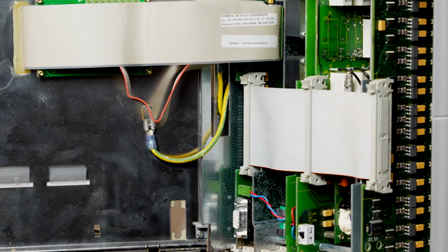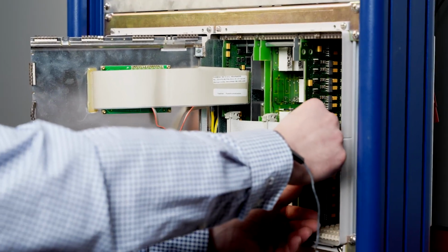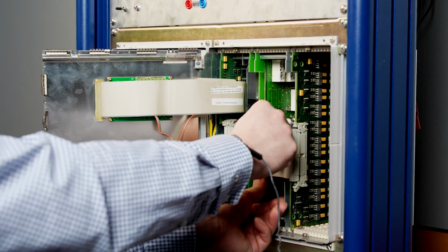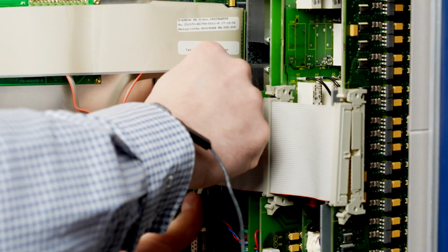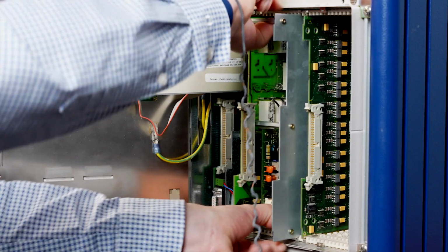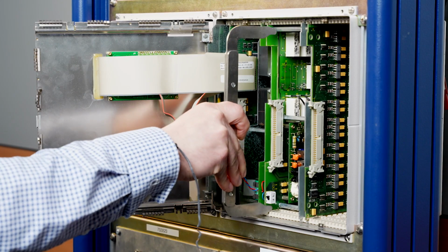Remove the assembly. Unlock the connectors on the power supply module and the input-output module by pressing the connector locks up and down. Now you have to remove the ribbon cable. Pull out the power supply module by hand. Alternatively, you could use the supplied unlocking bracket.